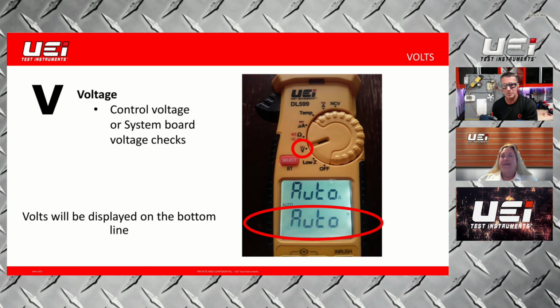Which is really nice, to be able to utilize volts and your current, your amps, all on one screen at the same time. So we'll check that one, check our incoming current draw — we know we have 0.23 — and we'll check voltage, going on this particular board from our common over to our line hot, which is what we're measuring with our amps. And there we go, 123.5. So the ability to check volts and amps at the same time — kind of like that.